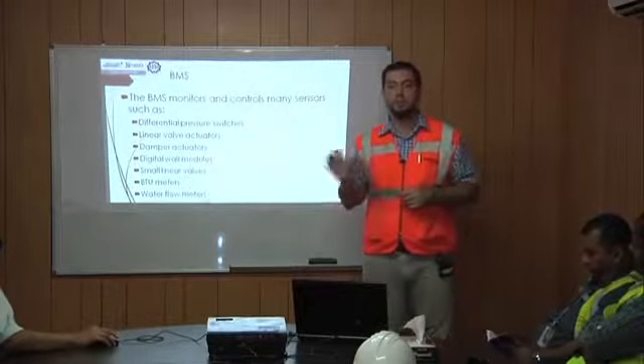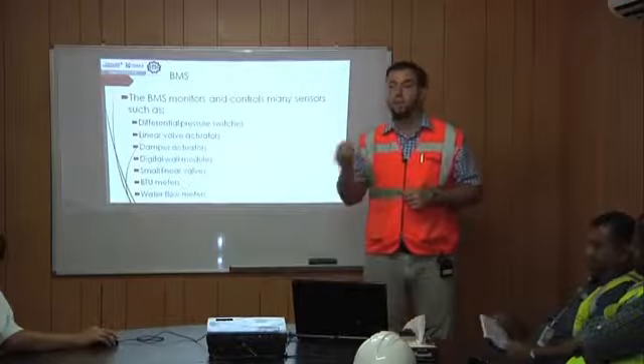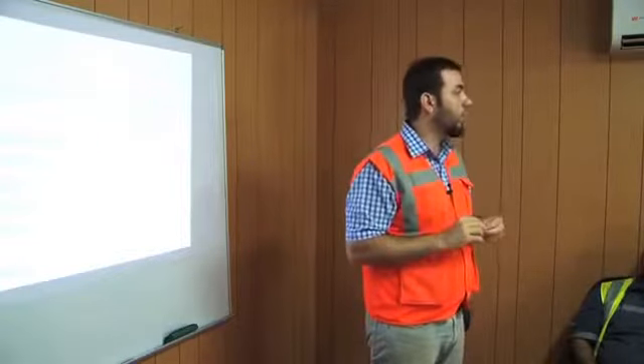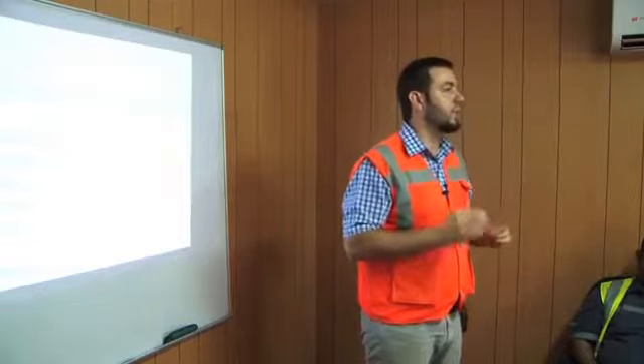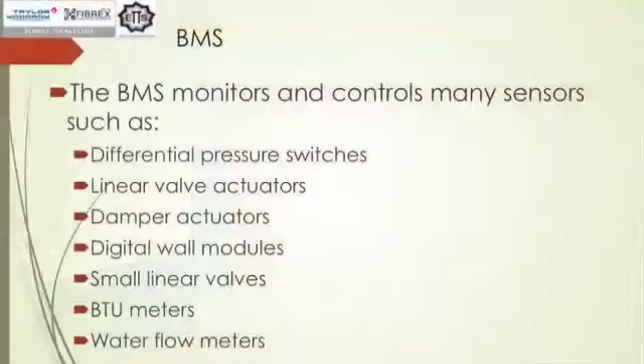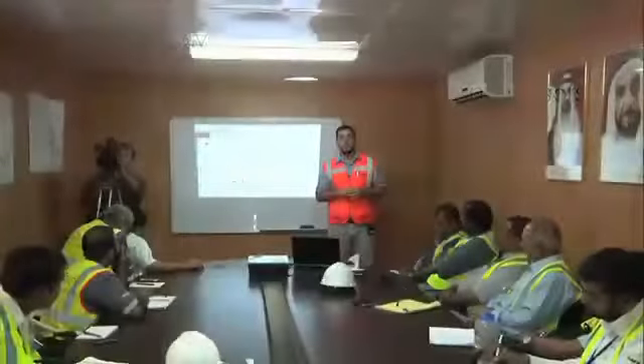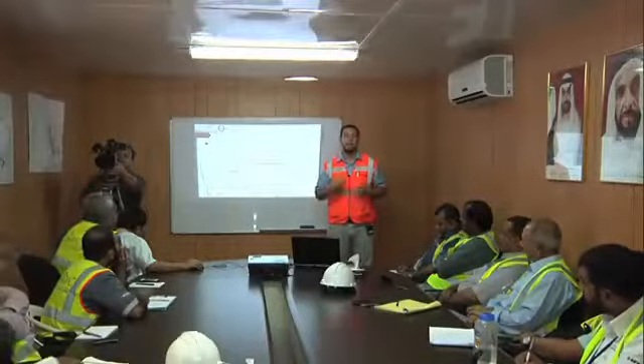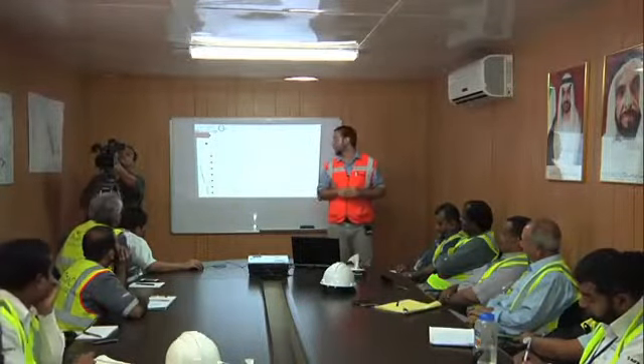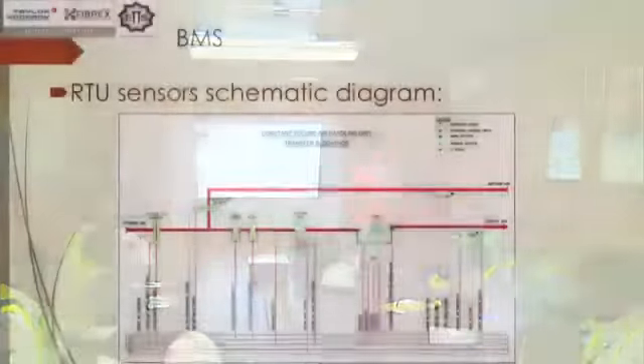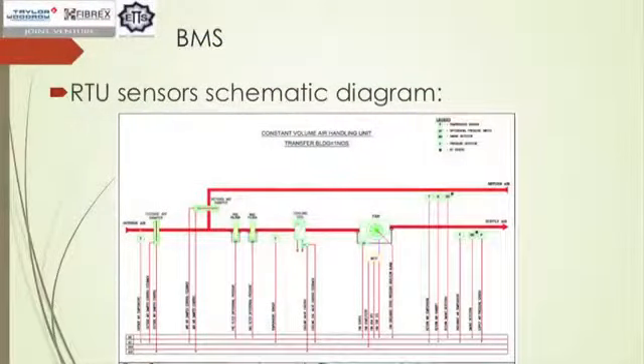Every single point, you can manage it and you can monitor it from the BMS graphics. You just click on this BTU meter, you go check the flow at this particular branch, check the temperature that is on the return and on the supply. There are 4 RTUs, and there are 2 main branches that are going, one to the provision to the Etihad Plaza, and one on the main branch in the pump room. 6 in total.